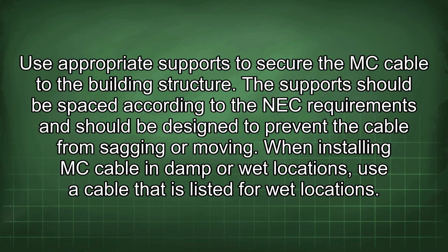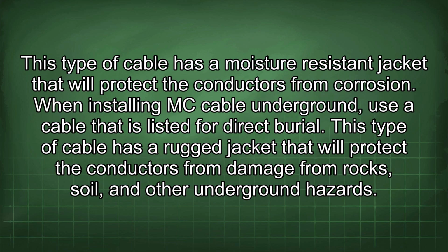When installing MC cable in damp or wet locations, use a cable that is listed for wet locations. This type of cable has a moisture-resistant jacket that will protect the conductors from corrosion. When installing MC cable underground, use a cable that is listed for direct burial. This type of cable has a rugged jacket that will protect the conductors from damage from rocks, soil, and other underground hazards.